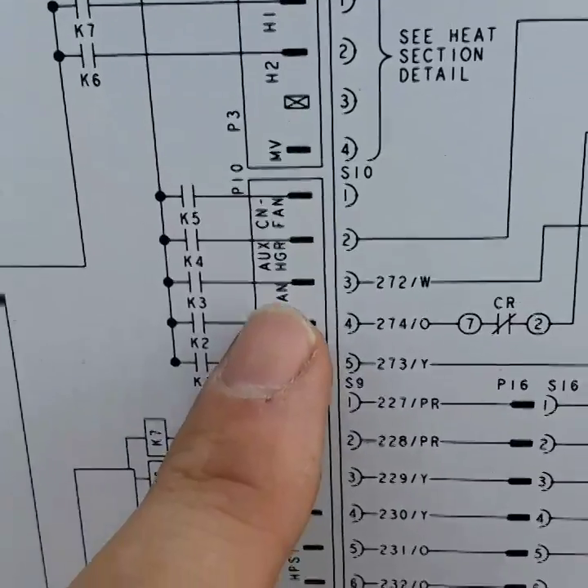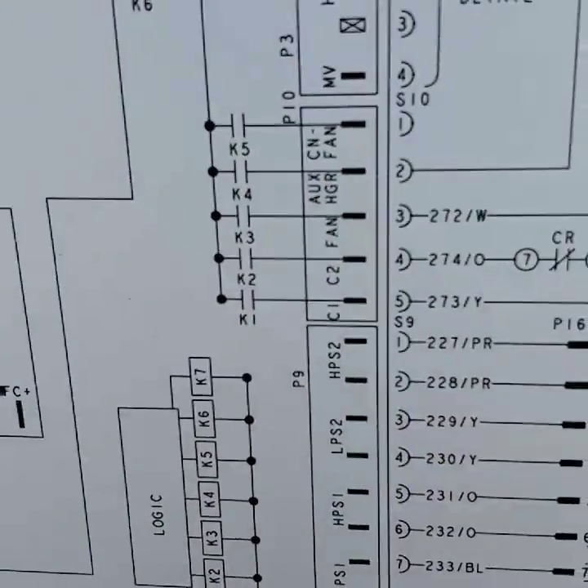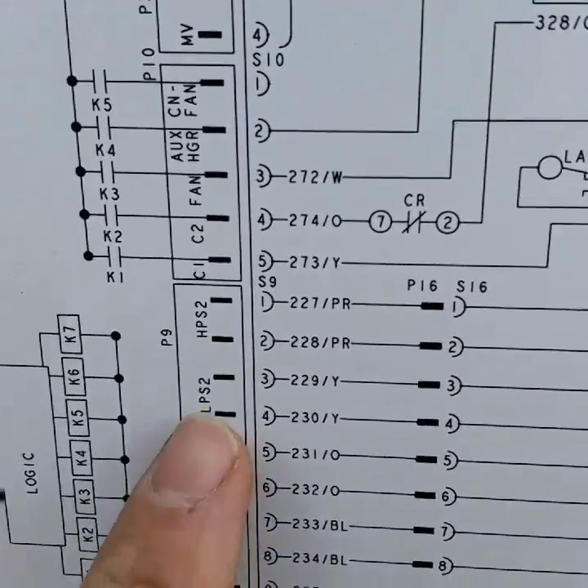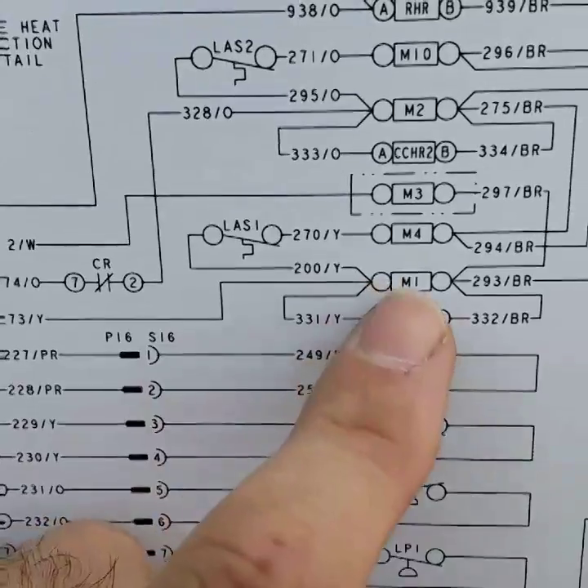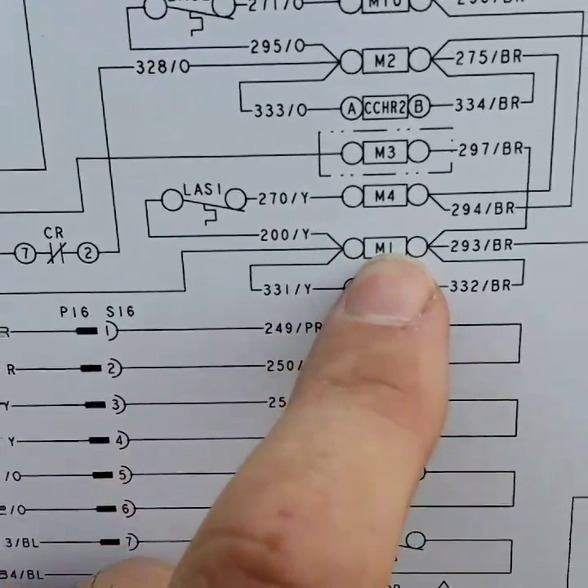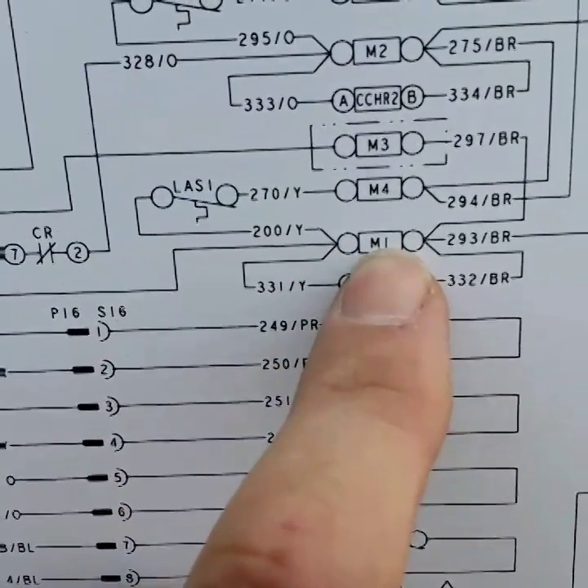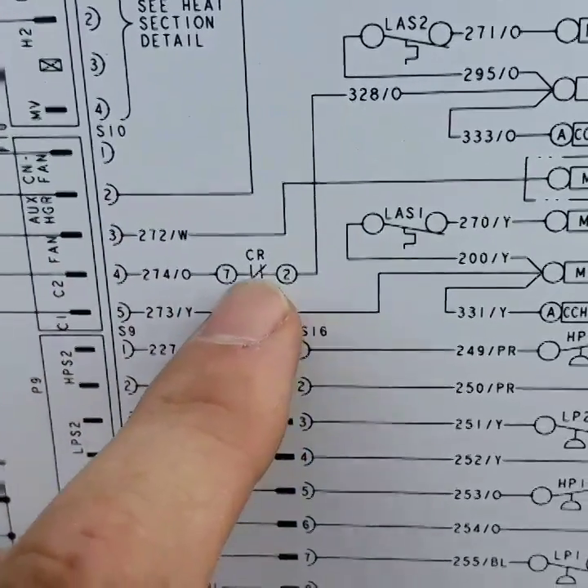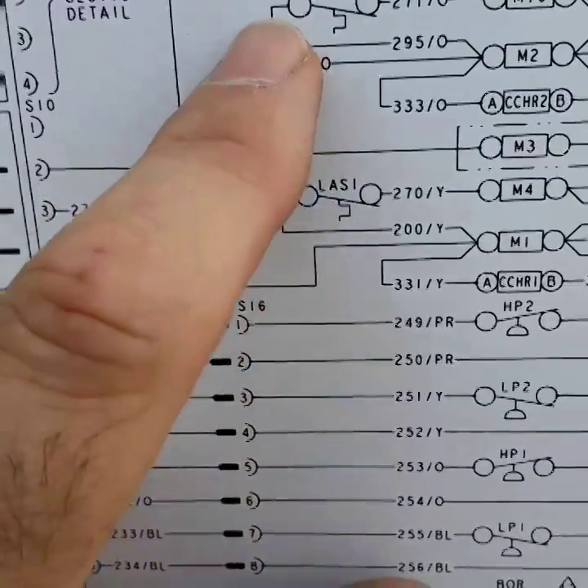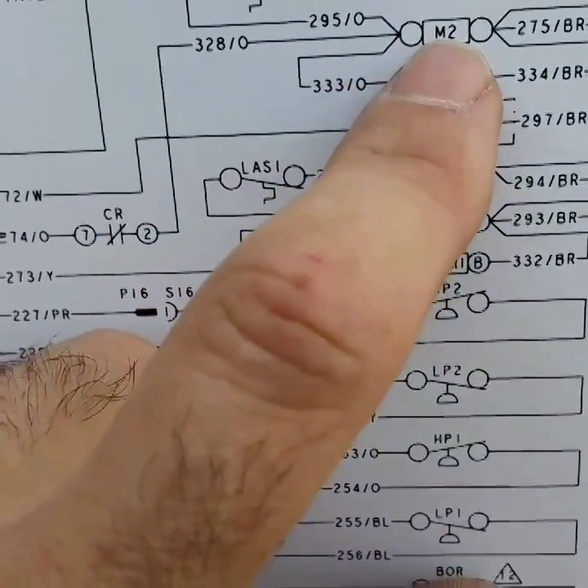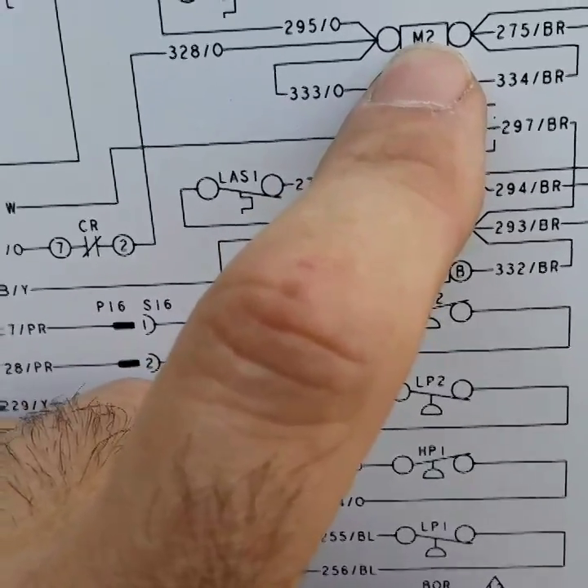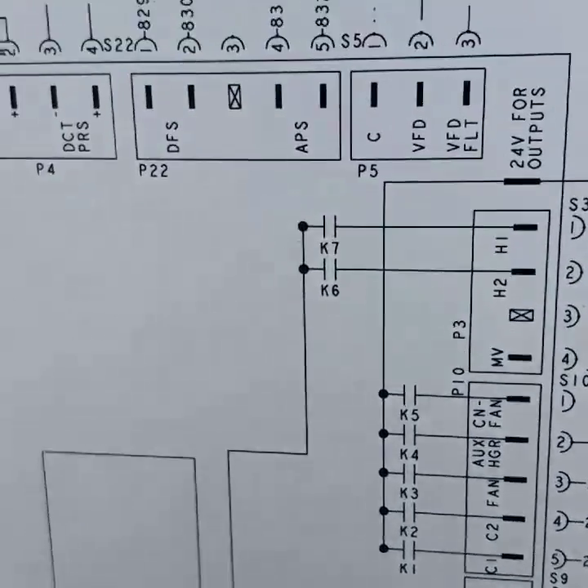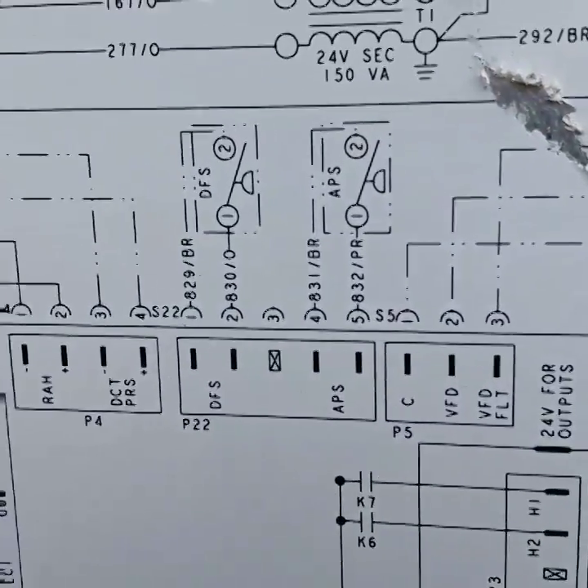The outputs include cooling 1, cooling 2, fan, etc. If we follow C1, for example, that will energize M1, which is the compressor 1 contactor coil. C2 power moves through a normally closed contact and up to M2, which is the compressor contactor for stage 2 cooling. So we have a problem somewhere in that circuit causing that breaker to trip.